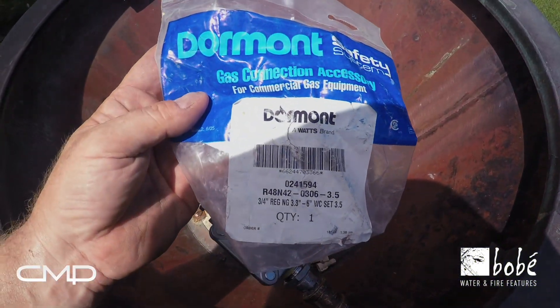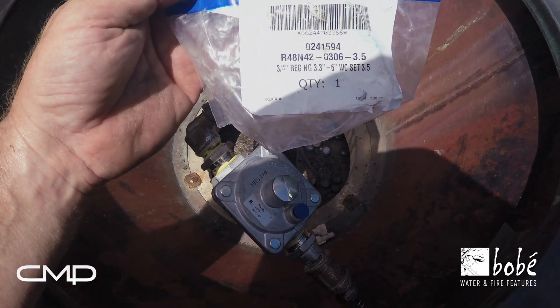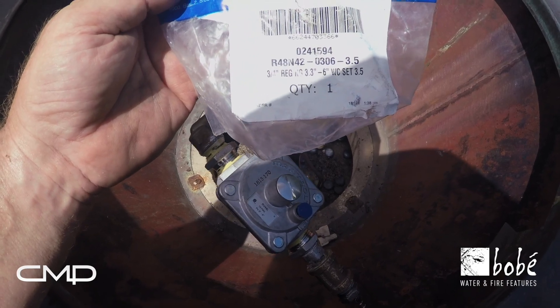Today we're using a Dormont regulator. It's preset to 3.5 inches of water column.